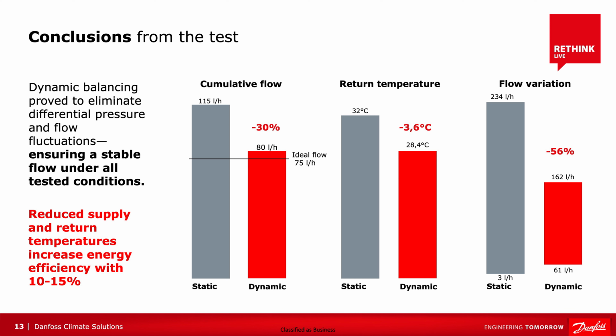Conclusions we can draw from the test: dynamic balancing proved to eliminate a lot of our differential flow and pressure fluctuations, and we have a stable flow under all tested conditions. The real benefit is that we saw reduced supply and return temperatures, and that allowed us to increase our energy efficiency in the entire system by 10 or 15%. That's where the proof is, in improving the entire heat pump system.